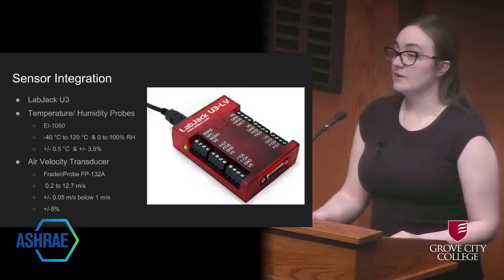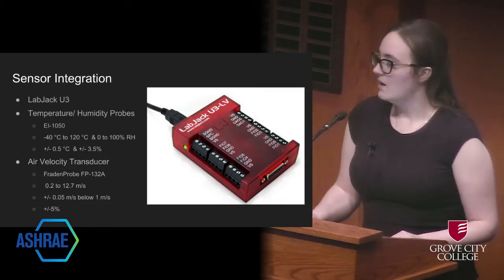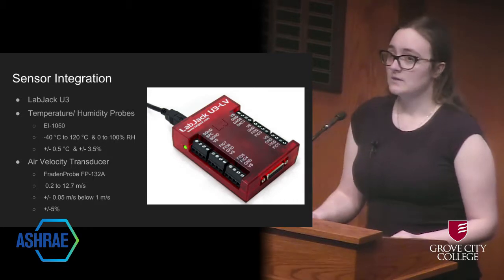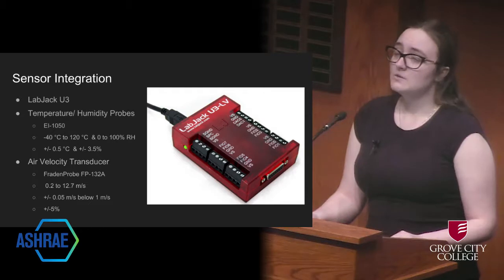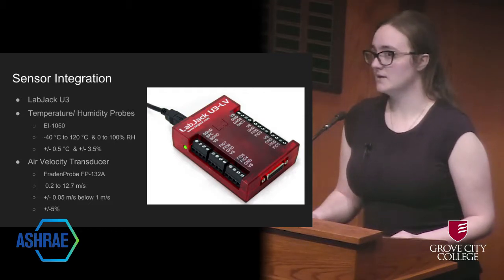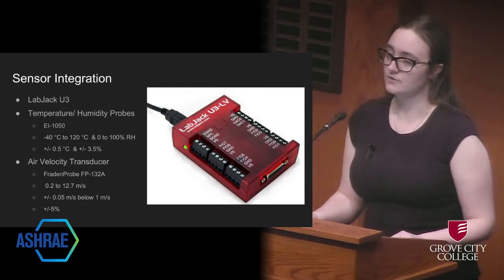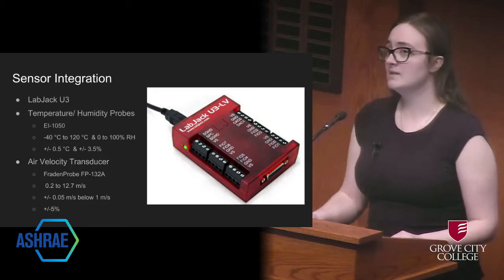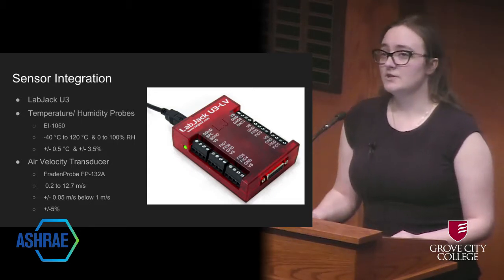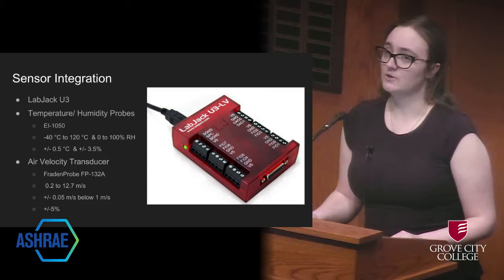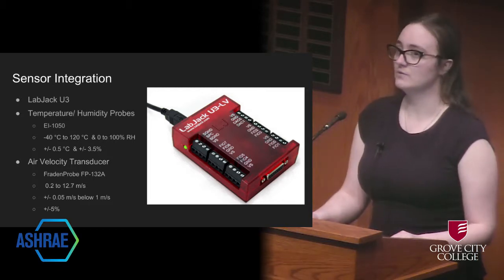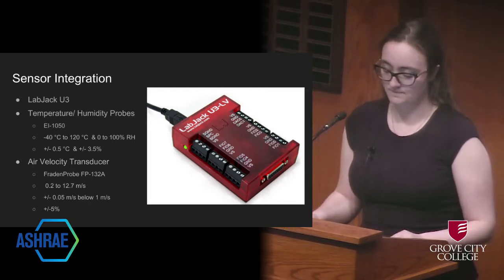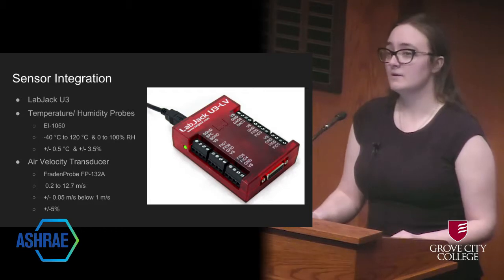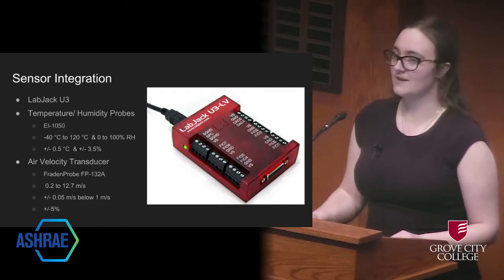To actually get the velocity from the sensor, the LabJack reads the voltage being outputted and puts it into a calculation, provided to us through the air velocity transducer's manual. Once put into this calculation, it converts the reading into meters per second, and this is shown to the user in the application.